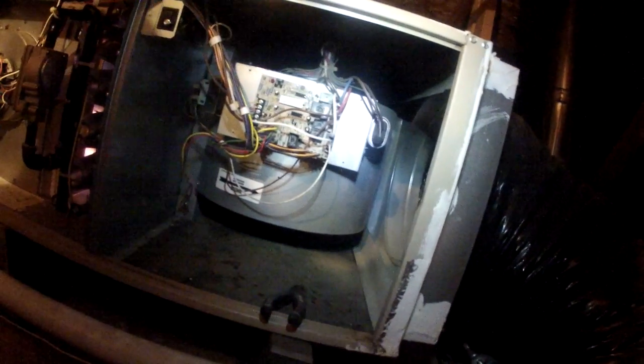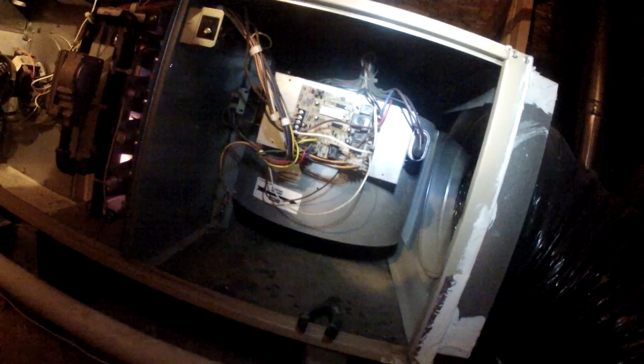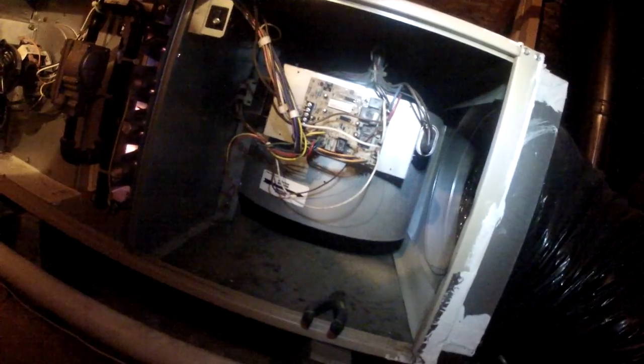So possibly something going on with the blower relay. Then it went off, and then at its normal time it came back on, like after the firebox, after the heat exchanger warmed up enough. And when the blower is supposed to come on, it actually came on and has stayed on.